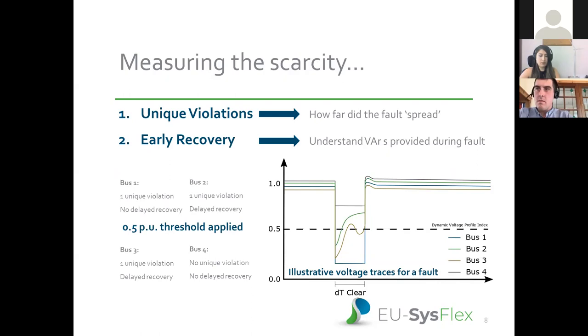So as you can see in those time domain examples, we run the model, put a three-phase fault on a bus, and then we just count the buses that go below that dashed line. We then calculate the percentage of buses which recovered during the fault. And the concept of this was to get a feel for how far the fault spreads and how springy the system is during the fault.